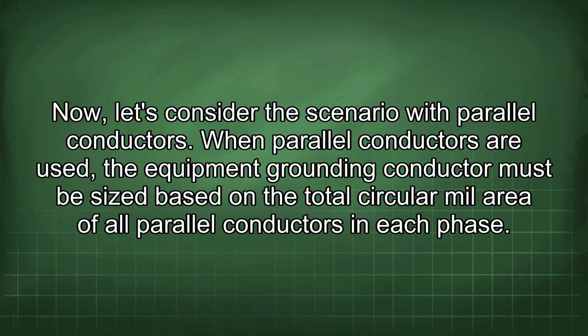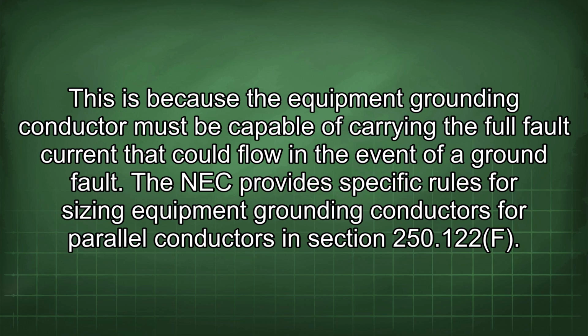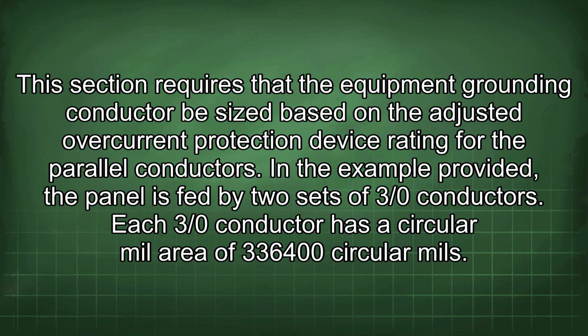Now, let's consider the scenario with parallel conductors. When parallel conductors are used, the equipment grounding conductor must be sized based on the total circular mil area of all parallel conductors in each phase. This is because the equipment grounding conductor must be capable of carrying the full fault current that could flow in the event of a ground fault. The NEC provides specific rules for sizing equipment grounding conductors for parallel conductors in section 250.122(F). This section requires that the equipment grounding conductor be sized based on the adjusted overcurrent protection device rating for the parallel conductors. In the example provided, the panel is fed by two sets of 3/0 conductors.